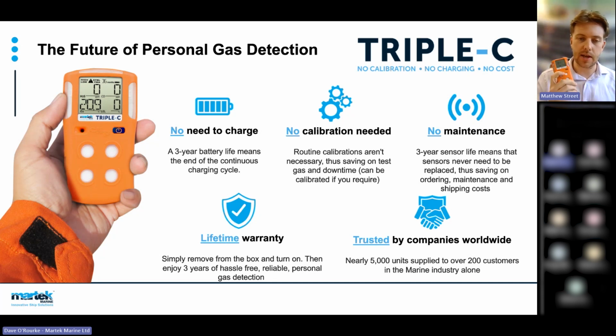This is a 3-year disposable gas detector. During those 3 years, it's designed never to be recharged—the battery will continue to run. No calibration is required. It comes with a certificate guaranteed for 3 years, and there's never any maintenance required. You'll never need to access the back of the detector or change any of the sensors inside it. There is a requirement to bump test, which I'll talk about in more detail later.